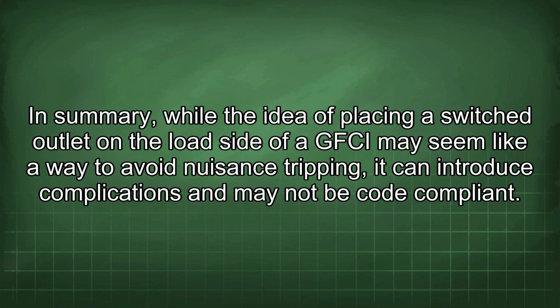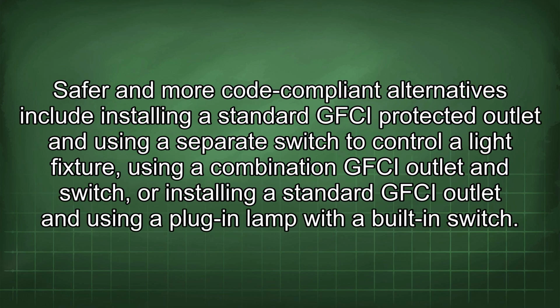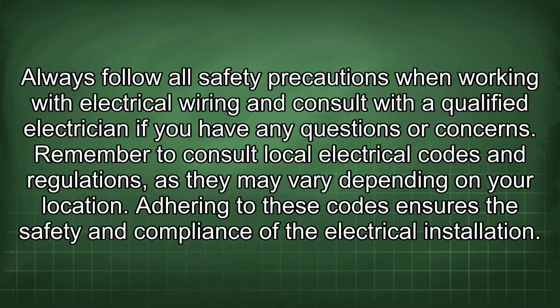In summary, while the idea of placing a switched outlet on the load side of a GFCI may seem like a way to avoid nuisance tripping, it can introduce complications and may not be code compliant. Safer and more code-compliant alternatives include installing a standard GFCI protected outlet and using a separate switch to control a light fixture, using a combination GFCI outlet and switch, or installing a standard GFCI outlet and using a plug-in lamp with a built-in switch. Always follow all safety precautions when working with electrical wiring and consult with a qualified electrician if you have any questions or concerns.